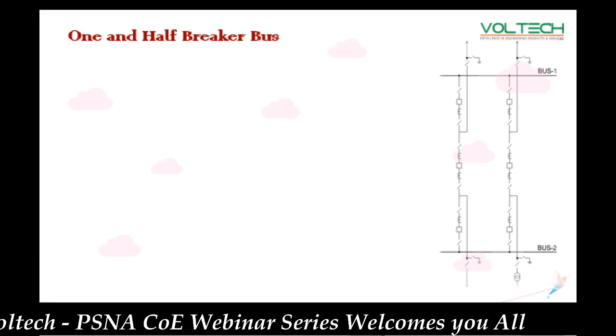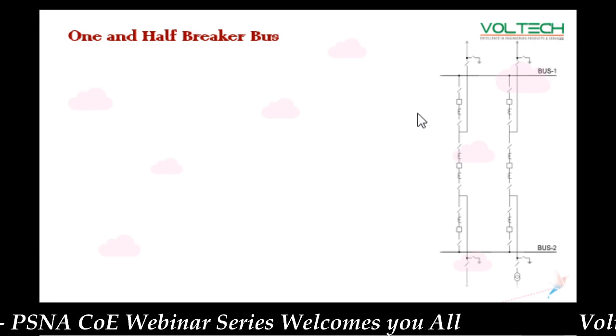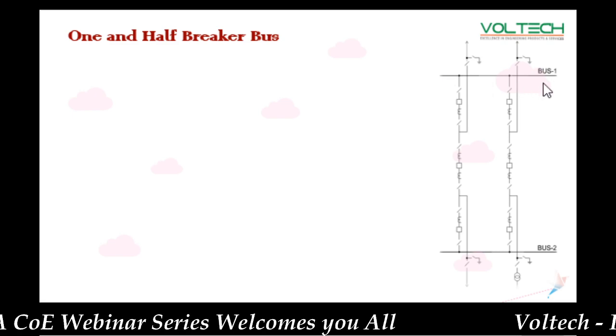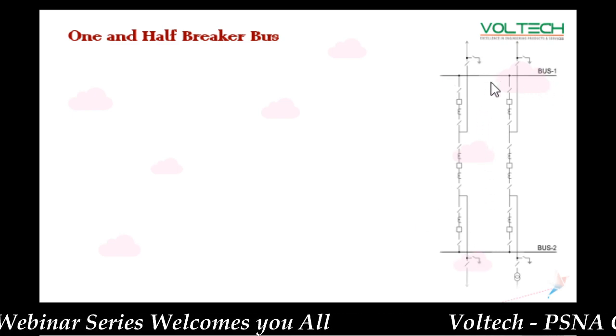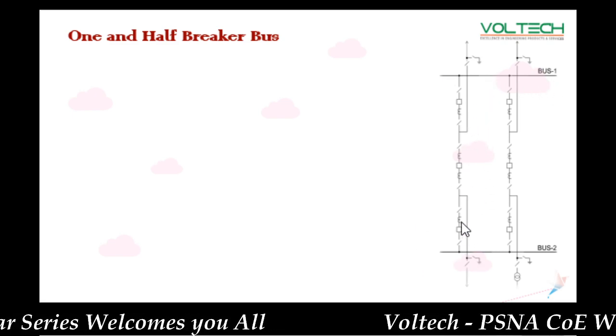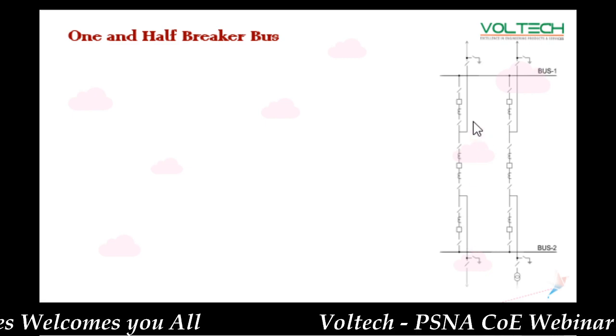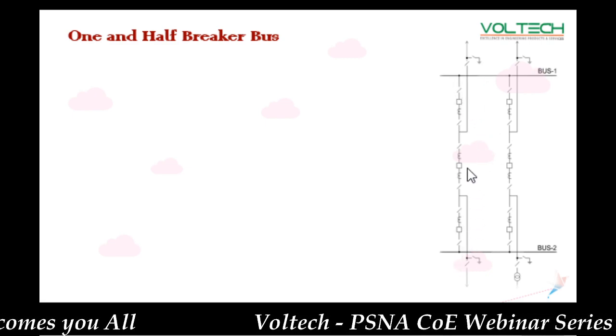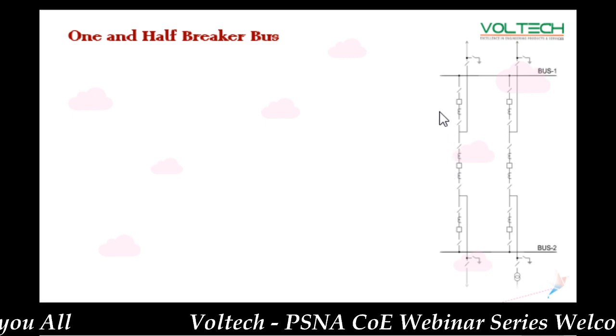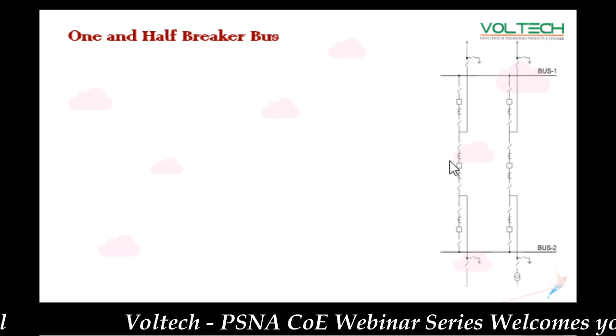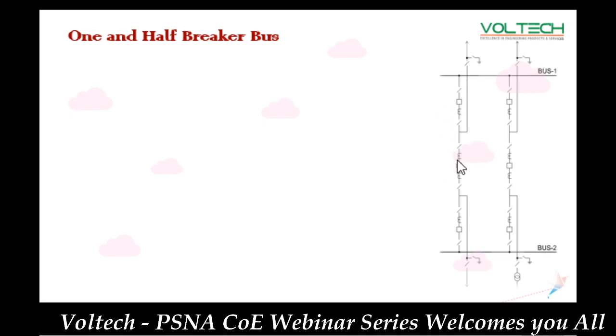The next one is the 1.5 scheme. I already told you 1.5 means 2 bus bars with 3 breakers. Here are breakers 1, 2 and 3. So these 2 bus bars are sharing the 1.5 breaker. So this is what is called the 1.5 bus.